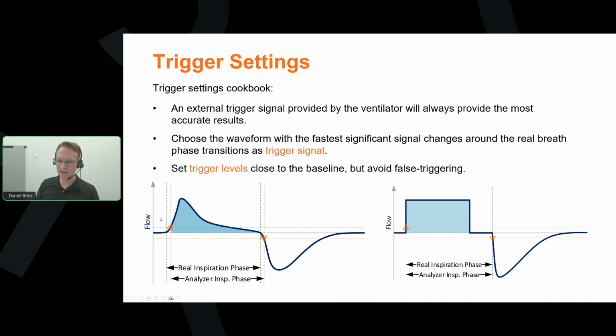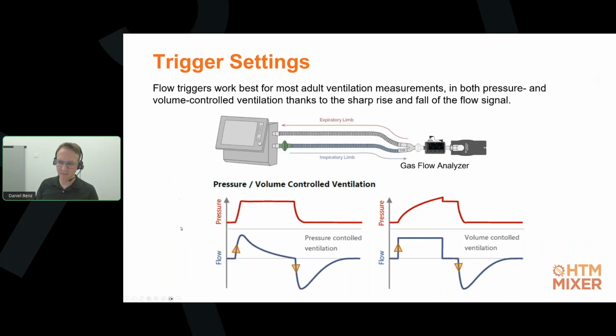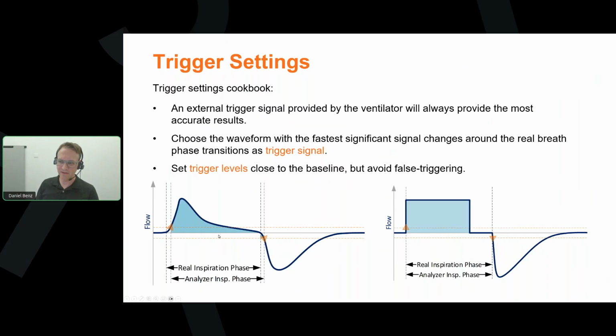Here on the left side, we have a flow waveform which is not as steep as in our example on the right side. If we have our threshold, for example, here at the dotted orange line, then we are missing a little bit of the start of our first phase, and we are also a little bit delayed at the end of the inspiration phase. So our measurements are going to be a little bit off.